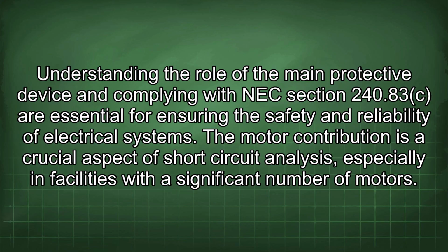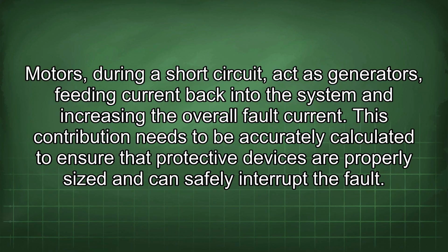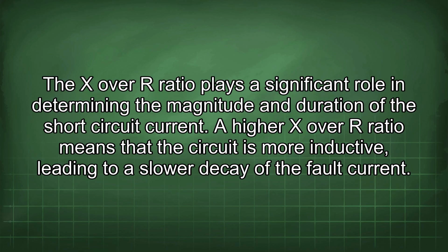The motor contribution is a crucial aspect of short-circuit analysis, especially in facilities with a significant number of motors. Motors, during a short circuit, act as generators, feeding current back into the system and increasing the overall fault current. This contribution needs to be accurately calculated to ensure that protective devices are properly sized and can safely interrupt the fault. The X/R ratio plays a significant role in determining the magnitude and duration of the short circuit current.